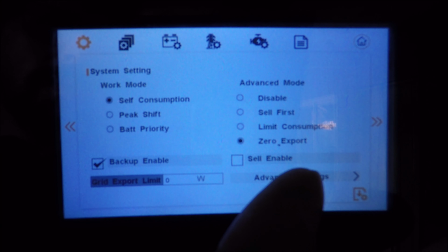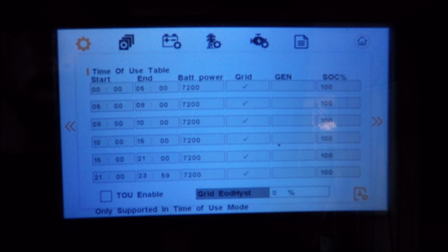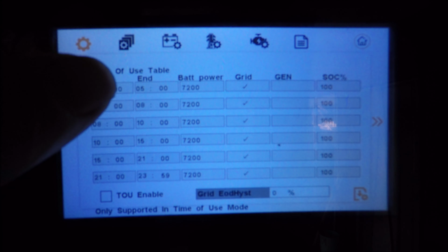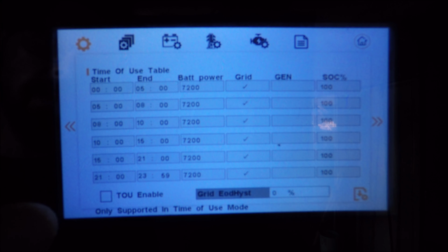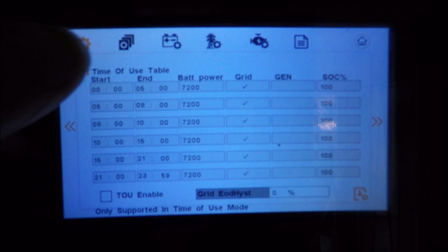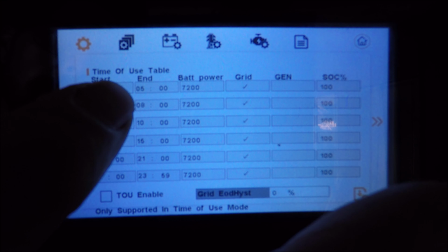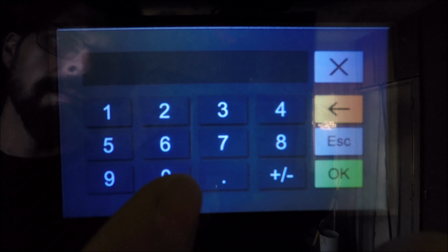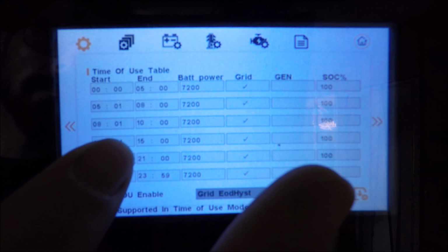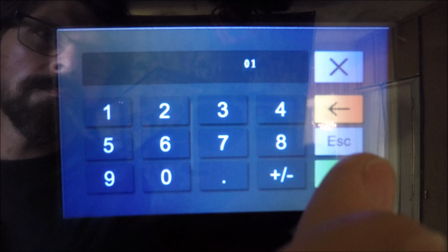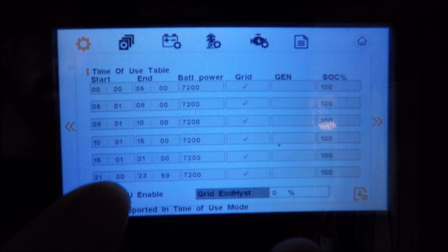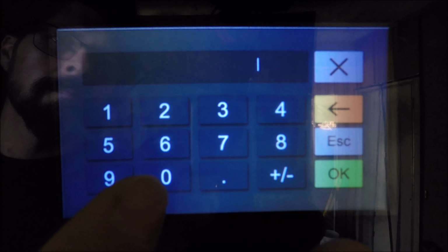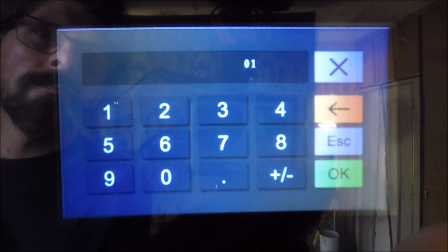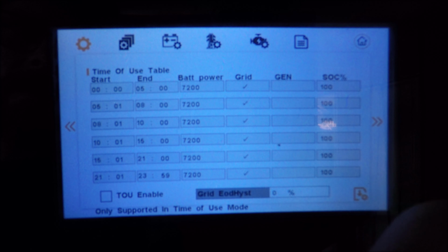So we're going to go in and take a look at time of use. Go into advanced settings. Now by default, you'll notice that the start and end times for each time of use entry, where we have 6 different entries, end and begin at the exact same time. You actually don't want this. So the first thing to go in and do if you're using time of use is to set these at 0, 1. There we go, and we're going to hit save.